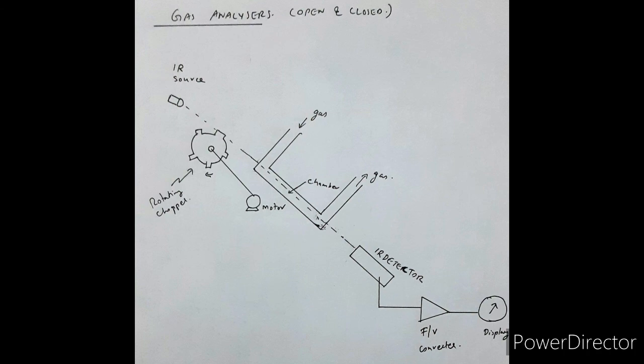This rotating chopper is driven by a motor, and the output from the IR detector is given to a frequency-to-voltage converter, which converts the frequency values into voltage and passes it to the display system.